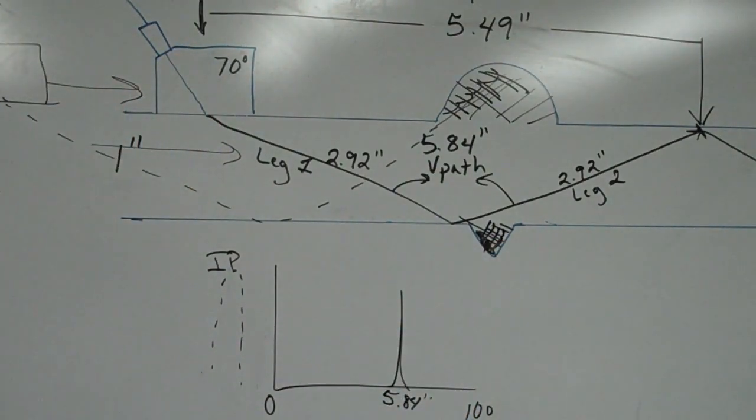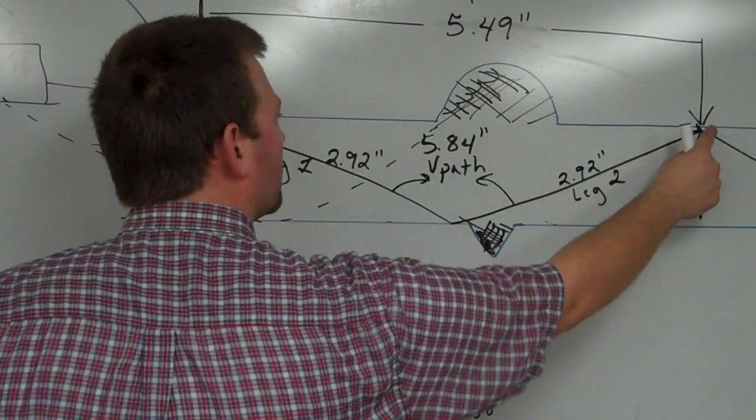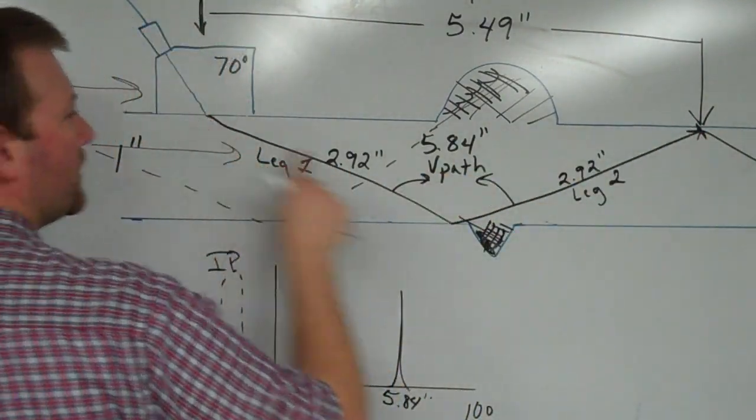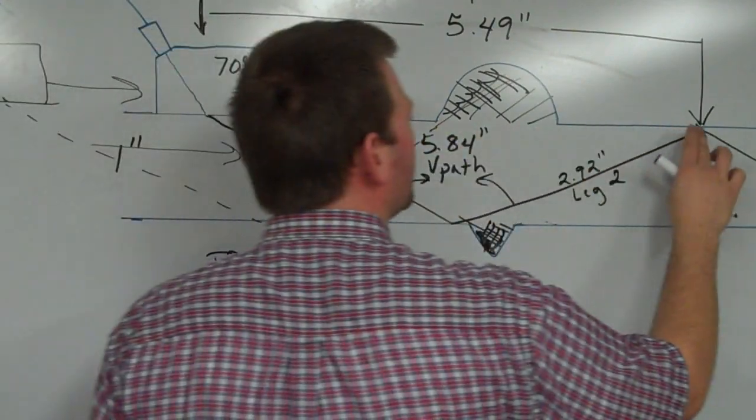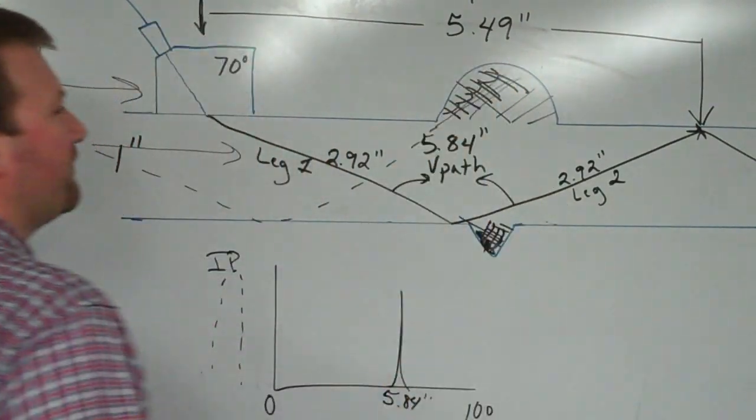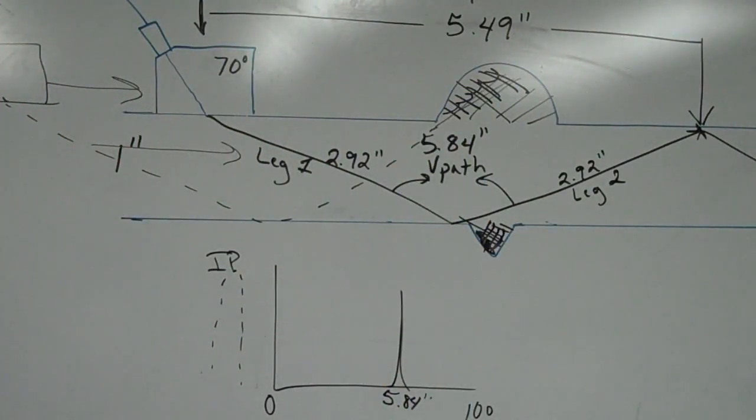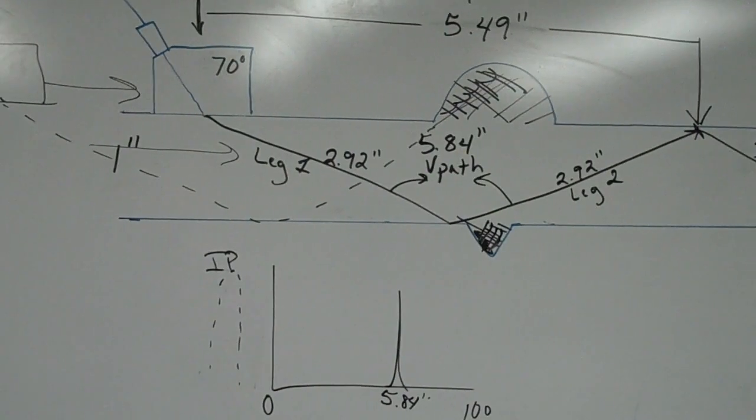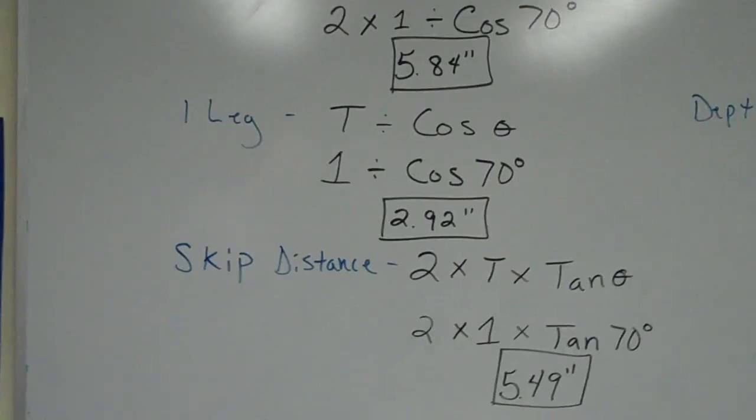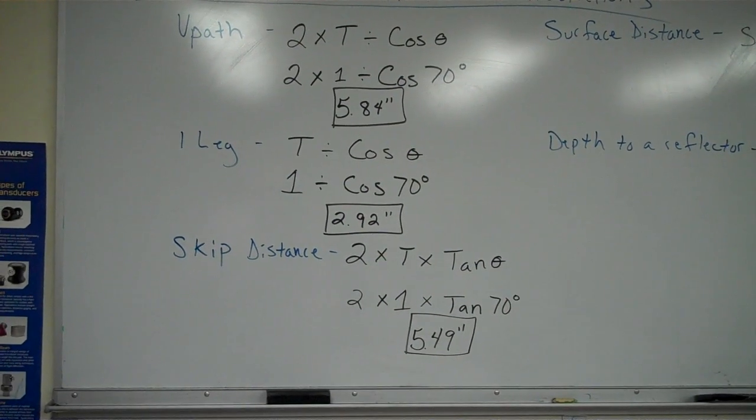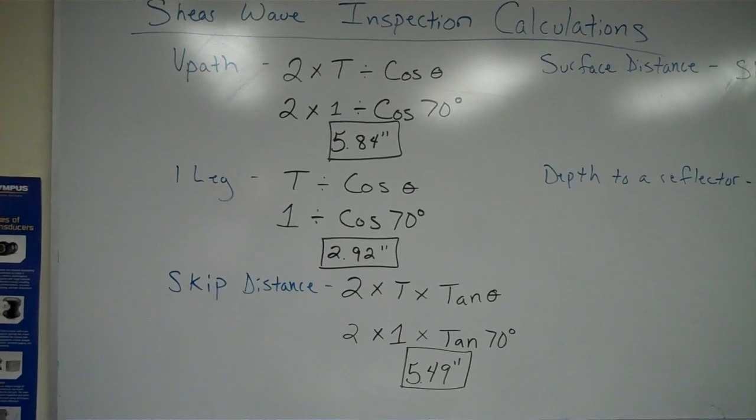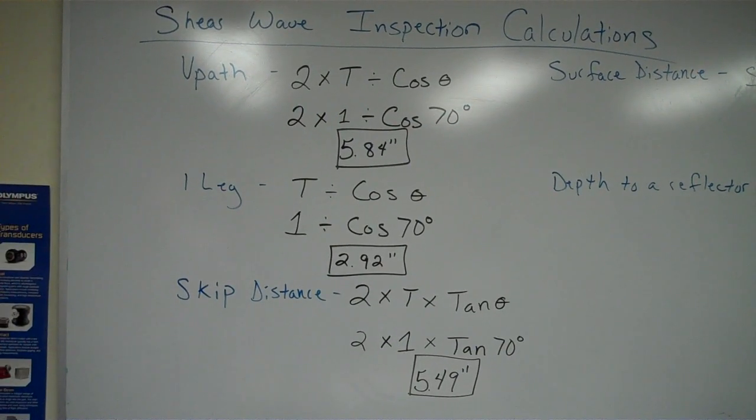But since there's not, we're just looking for this distance so we know where the sound enters, where it bounces at the bottom, and then where it's going to bounce again at the top and head back down. That way we can control our distance away from the weld. If we put the end of our skip distance right here and we move our transducer back like this, where our skip distance is right there.